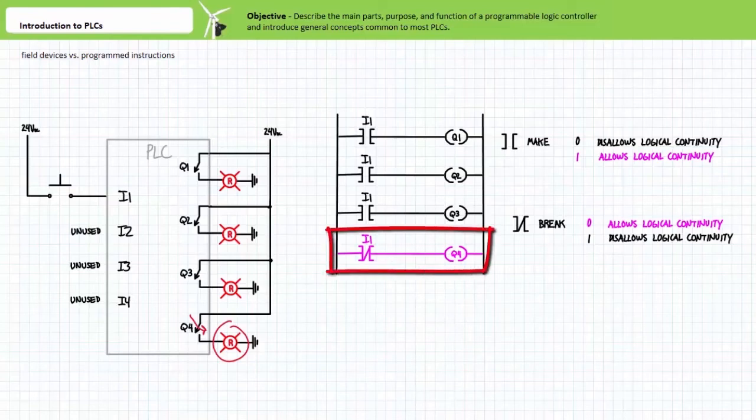Consider a normally open field input switch on input 1 logically instantiated three times using a make instruction and a fourth using the break instruction. The break instruction, essentially the opposite of the make instruction, allows logical continuity anytime the field input sends a logical 0 to input 1 and disallows logical continuity anytime the field input device sends a logical 1 to input 1.